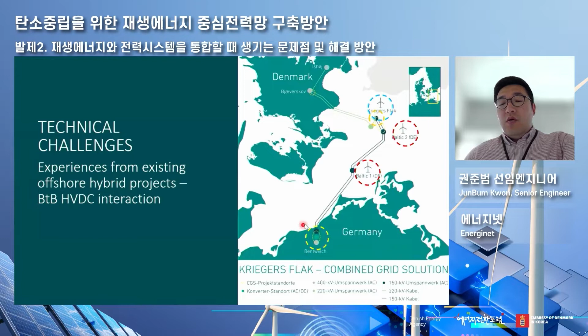Kriegers Flak system has 600 megawatts of wind power, and there was also 400 megawatts of existing offshore wind in Germany. There is a major offshore converter here that changed the voltage of the existing offshore pipe. To the east is Denmark, and there is an island here that is not synchronized with Germany, so they have back-to-back HVDC to synchronize the frequency.